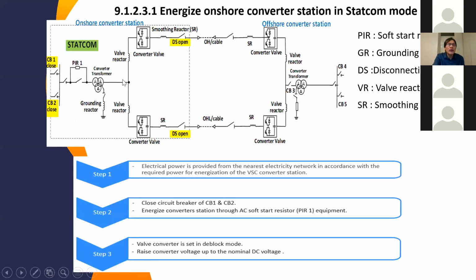This is an example of the circuit here. For the first step, when we energize in STATCOM mode, we close the circuit breaker which is connected to the AC substation in onshore. This disconnector here still remains open. There is no connection to the offshore converter station. So when this circuit breaker is closed, we can energize the converter station through the pre-inserting resistor here. So when we energize here, the valve, the converter, is set to block mode, and we raise the voltage up to nominal voltage. So by this, we energize the onshore converter station.